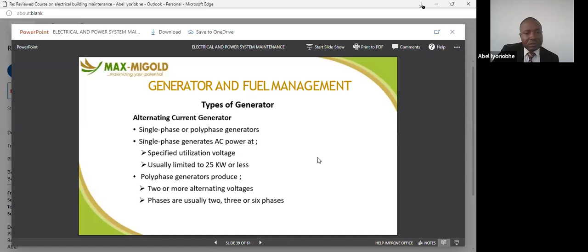As I said earlier, for installation of a generator, there are things you need to put in place. You don't just say, this building is big, let me go for 10,000 kVA. It doesn't work like that. You need to pay attention to the load in that building. How many loads? What is the capacity of each load? One of the things in selecting a generator is to determine the sum total wattage, the total power in that building. It could be 1,000 watts. If you have 1,000 watts in a facility, do you go for exactly 1,000? No, you can go for 1.3 or 1.15 to give some allowance so that your generator will not be overstressed.